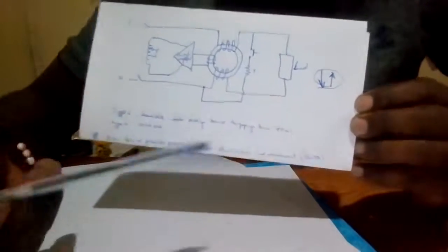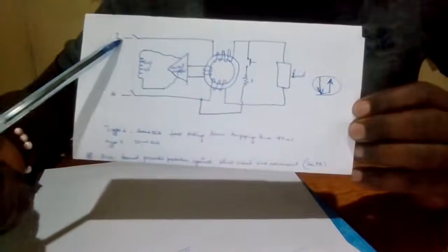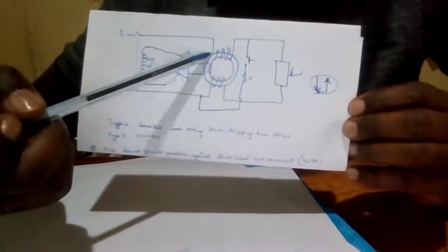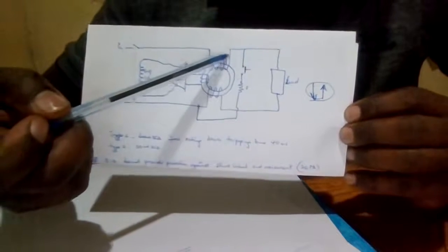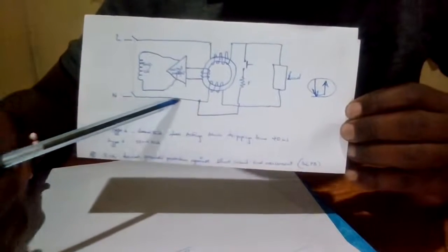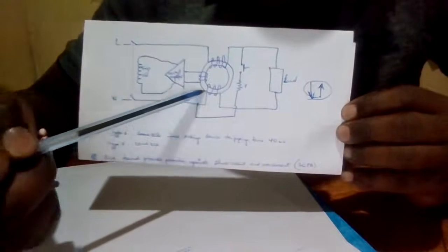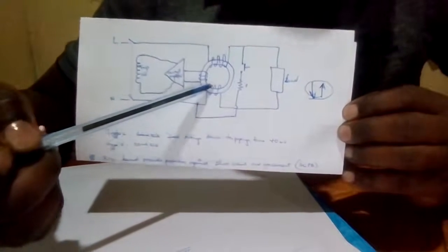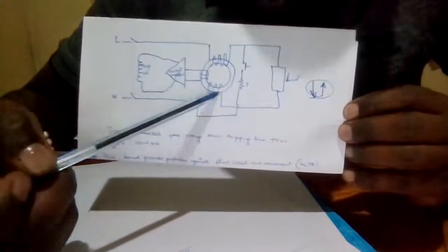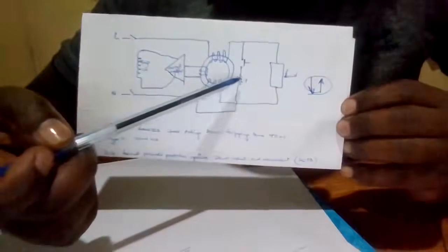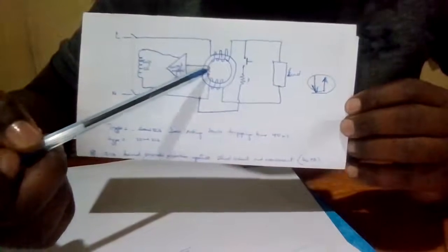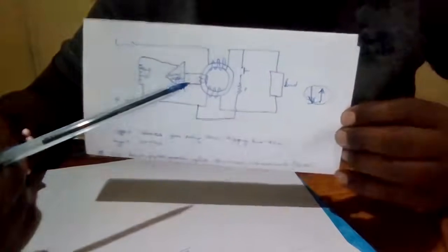So for this, if you can see very well, this is how it is arranged. We have a live wire and a neutral wire. Now this neutral comes and passes through the toroid and goes out to the load. The same applies to the live, which passes through the toroid with the same number of turns as the neutral and then goes to the load. Now, if this and this are equal, the resultant will be zero. That is how this philosophy is supposed to work.